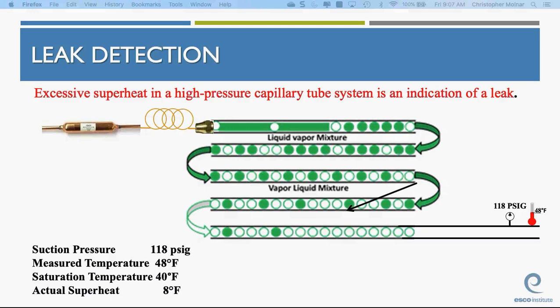Excessive superheat, if it's a fixed metering device, that will be a cap tube or a fixed orifice. Excessive superheat is an indication of a leak because there's a shortage of refrigerant. If it's a TXV, we do not charge or measure by superheat. We use subcooling, different story. But for the purposes of the EPA exam, excessive superheat in a high-pressure capillary tube system is one indication of a leak.